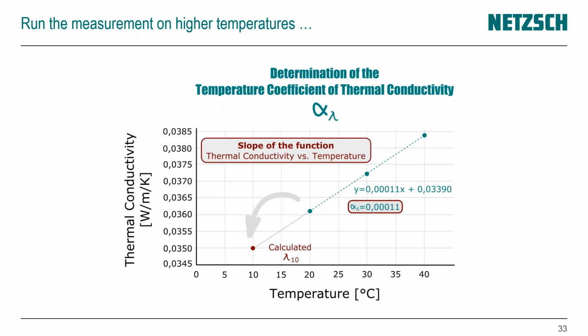In this plot, you see 3 measured points at 20 degrees C, 30 degrees C, and 40 degrees C. From this linear function of thermal conductivity over temperature, you can calculate the slope of the function, which is the so-called alpha lambda, the temperature coefficient of thermal conductivity. And by knowing this value, you can extrapolate from the straight line to a calculated lambda 10, which can be remeasured afterwards to get a feeling if there is a deviation and to get a feeling where the deviation comes from, and to help you through that process and to overcome the challenge that you don't have a feeling which influence is coming from humidity and condensation.